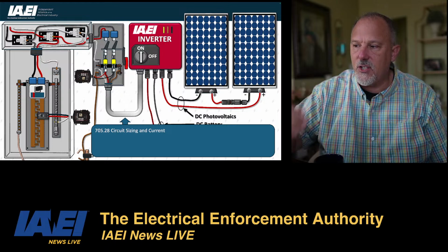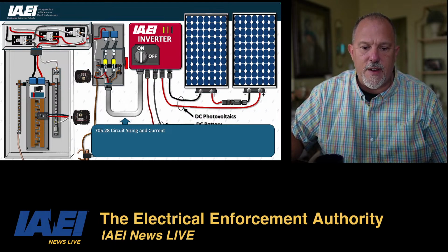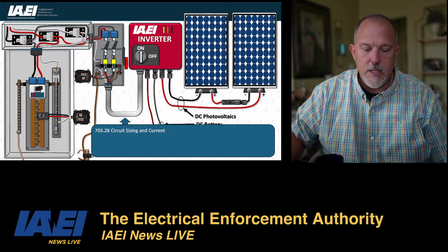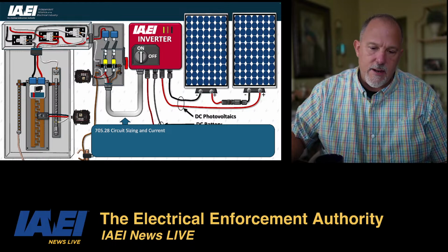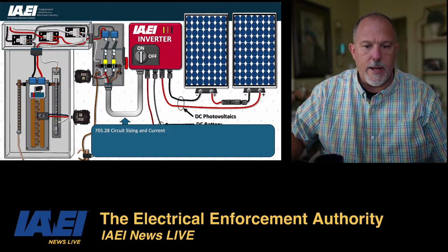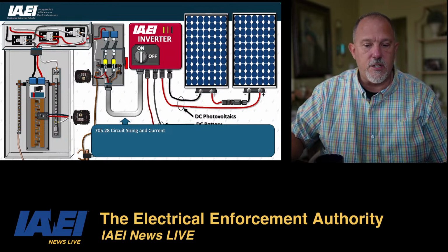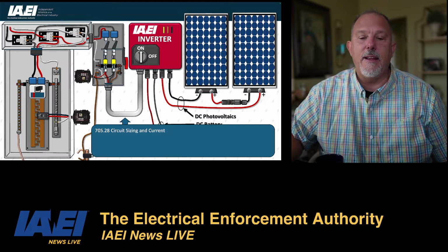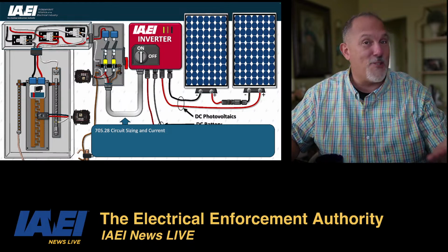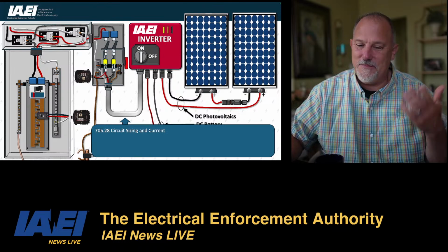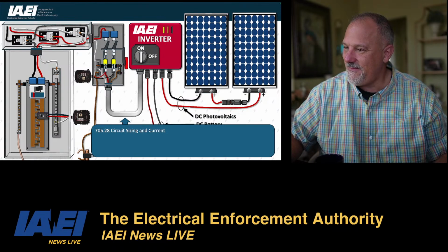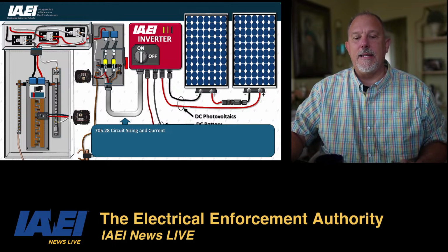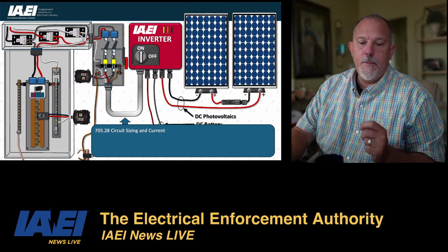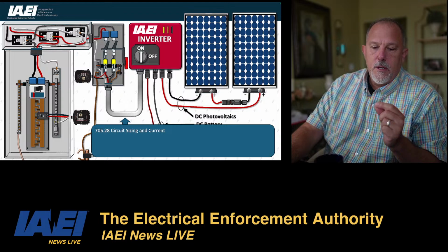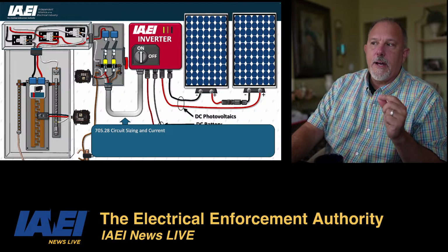But let's talk about circuit sizing. If you look at 705.28, 705 is not a very large article. It has some important information in there. Your IAEI inverter, look for a distributor near you, Willie. So just saying. 705.28 says you've got to determine what the current is.